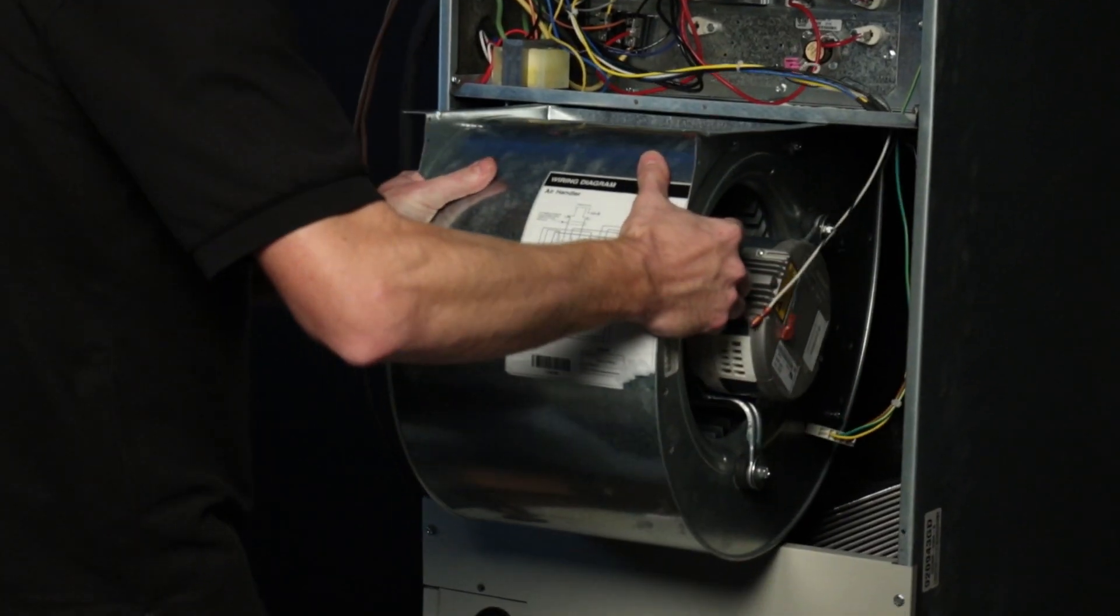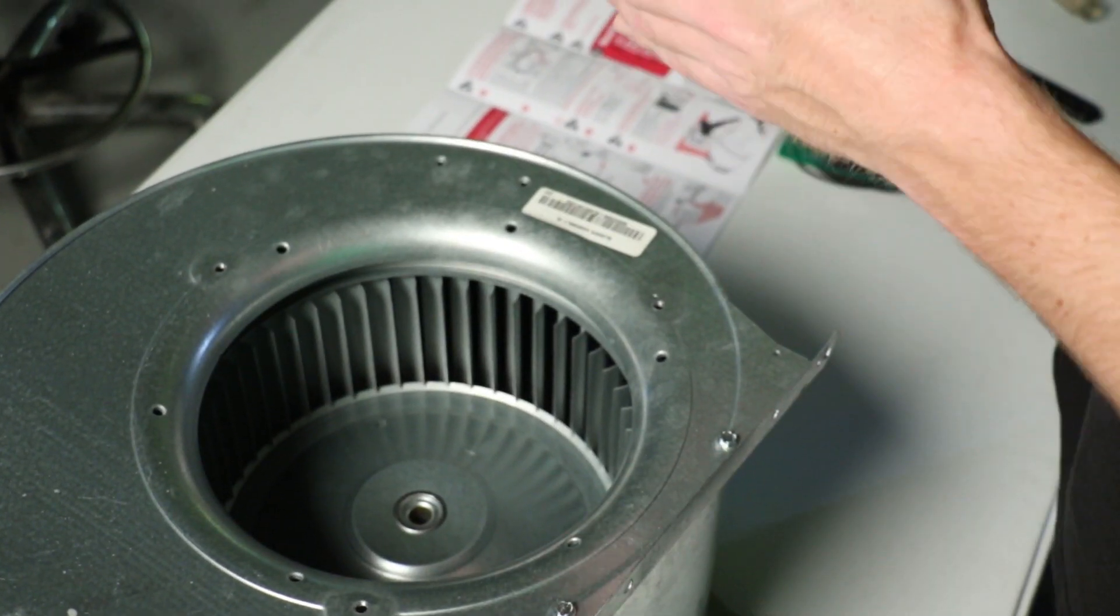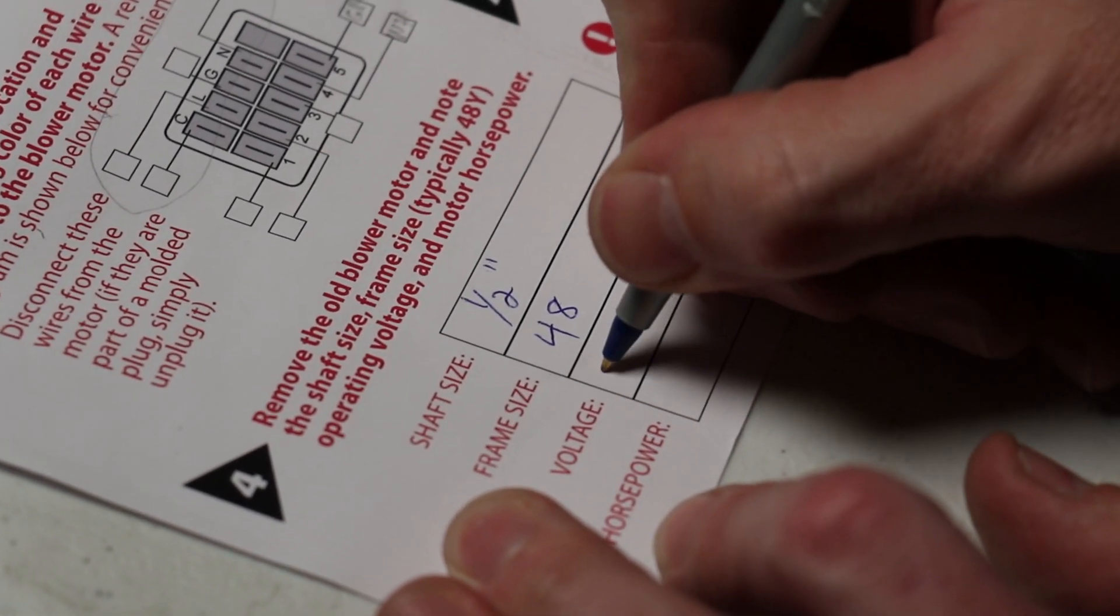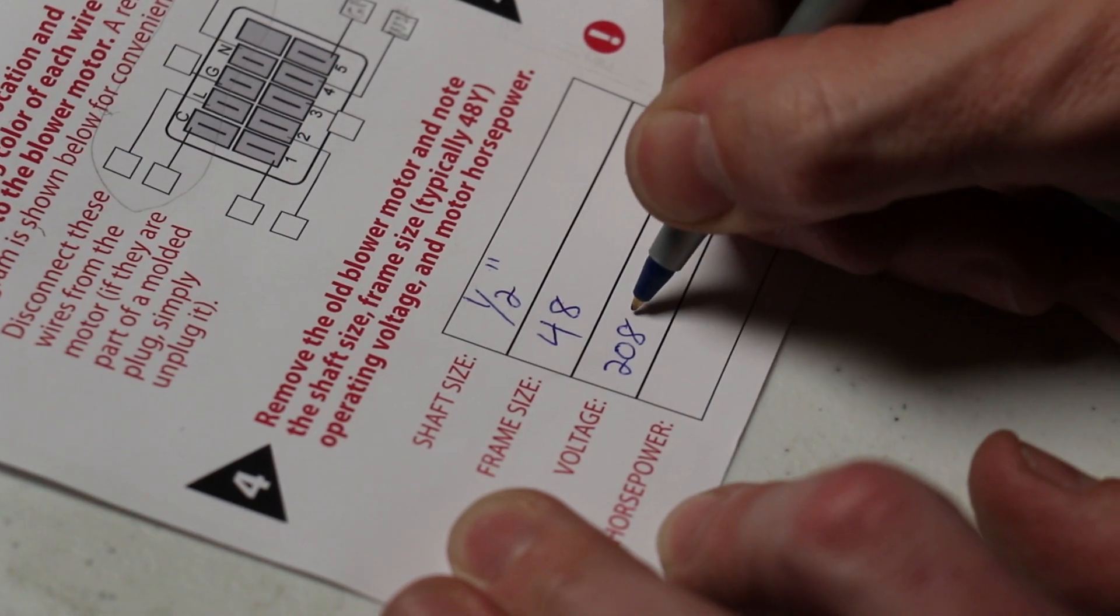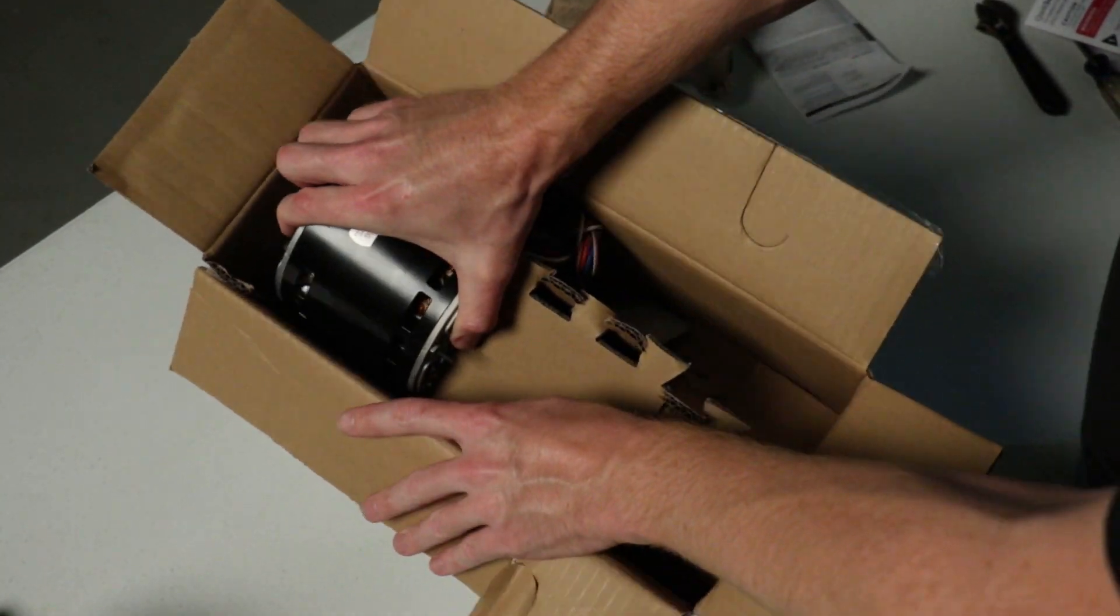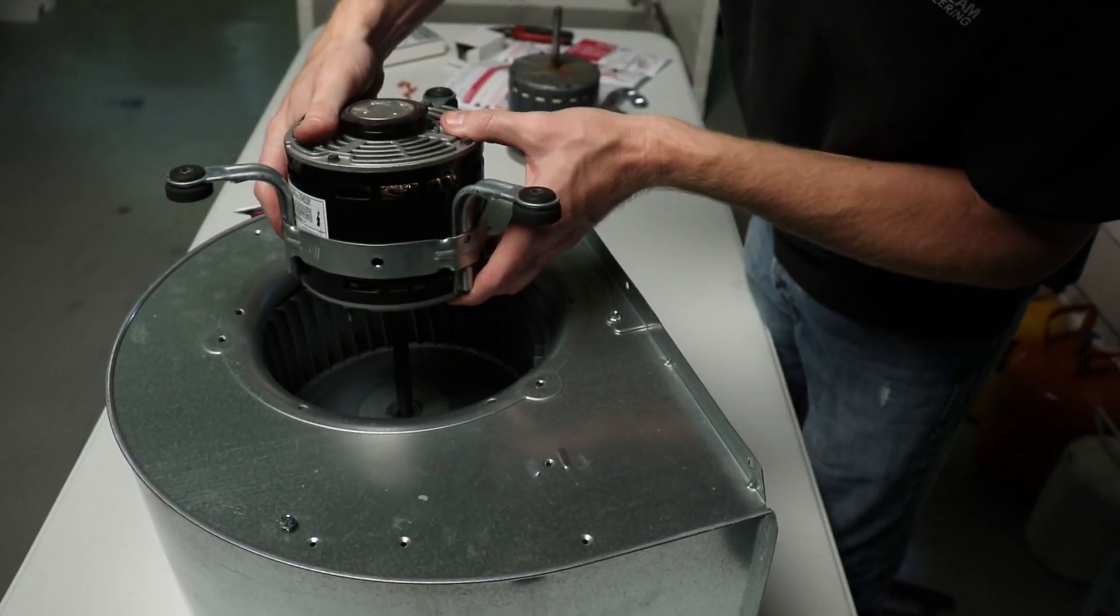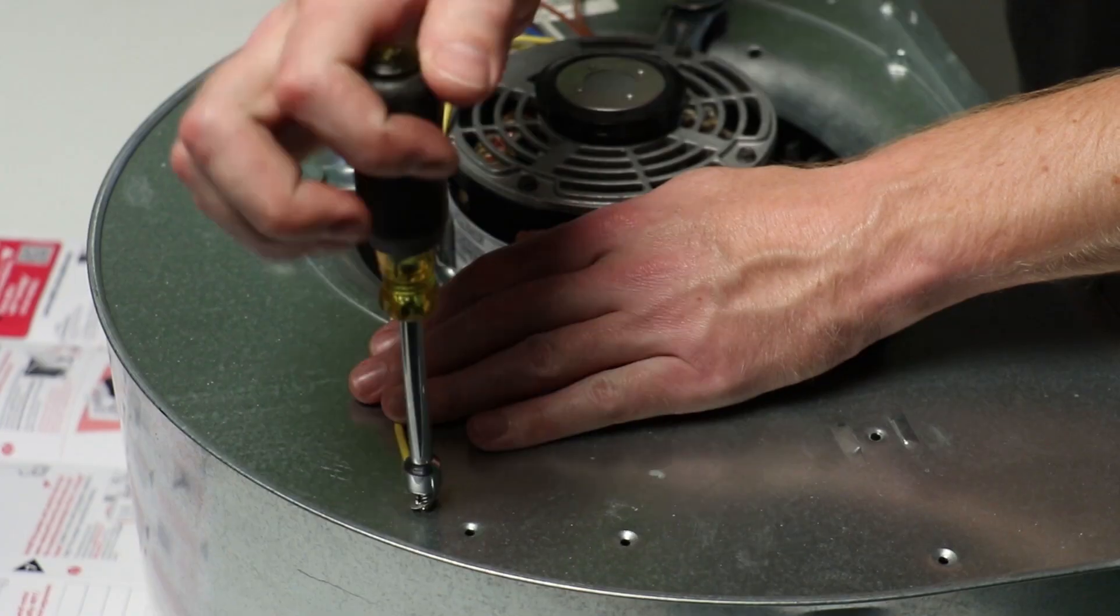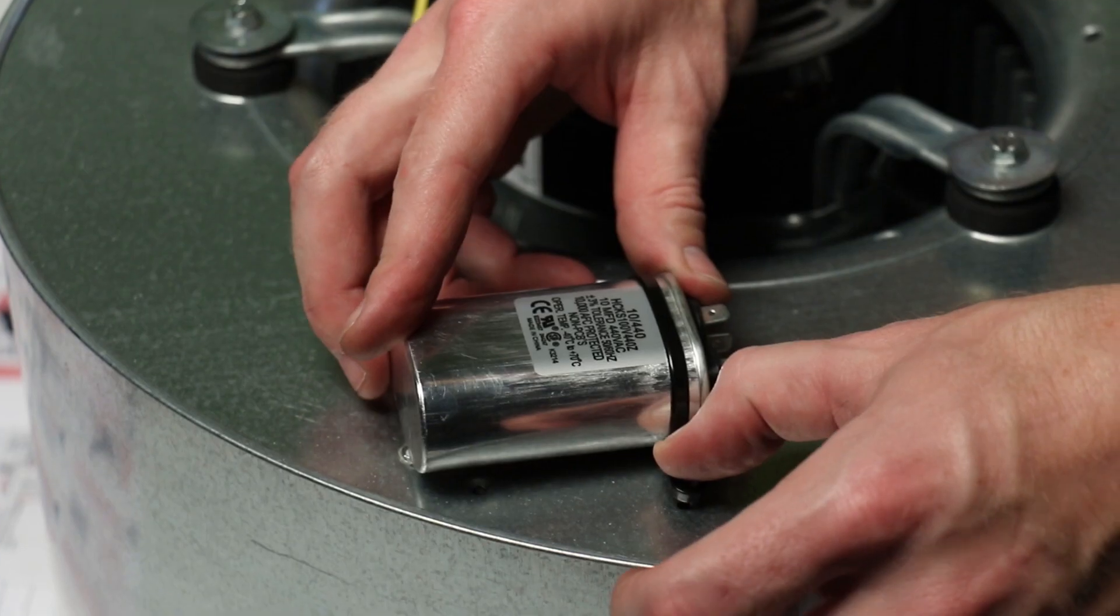Step four is to remove the old blower motor and take note of the shaft size, frame size, operating voltage, and motor horsepower. Write these values down in the instruction sheet. Step five: install a new permanent split capacitor blower motor with the specifications noted in step four. Properly ground the motor and mount the capacitor in a secure location.